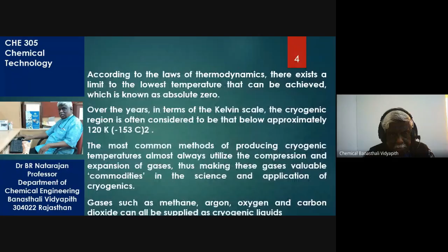Ambient air is compressed to 6 bar, 6 atmospheres. Then purification for removal of water and carbon dioxide, because air contains small quantities of water and carbon dioxide, and I have to remove them, otherwise water will form ice and CO2 will form dry ice at low temperatures. So I have to get rid of the water and CO2. So first dust removal, compression, then removal of water and carbon dioxide. Then I cool down my air to minus 173 degrees, which is close to the liquefaction point.